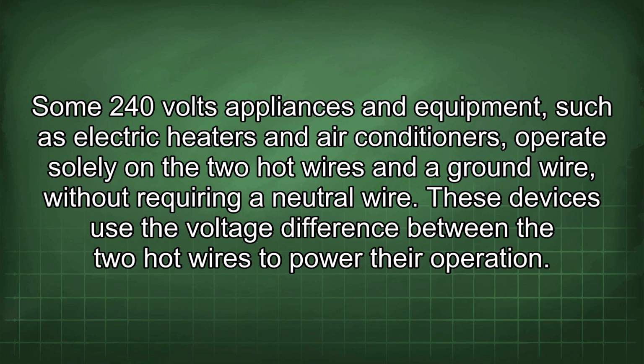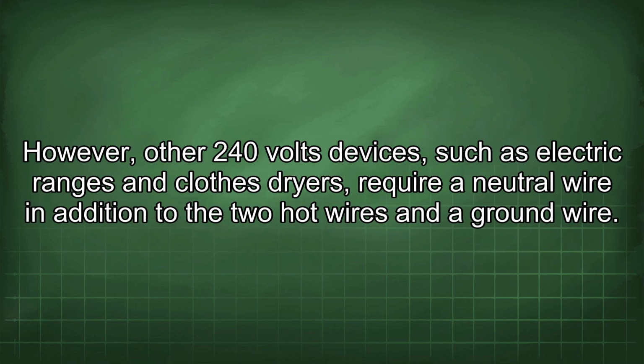Some 240-volt appliances and equipment, such as electric heaters and air conditioners, operate solely on the two hot wires and a ground wire without requiring a neutral wire. These devices use the voltage difference between the two hot wires to power their operation. However, other 240-volt devices, such as electric ranges and clothes dryers, require a neutral wire in addition to the two hot wires and a ground wire.